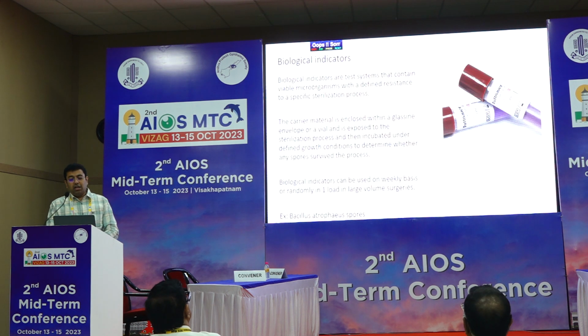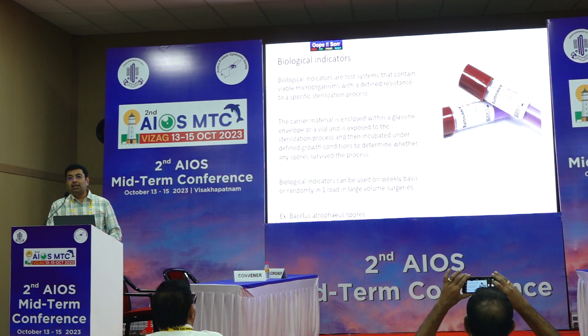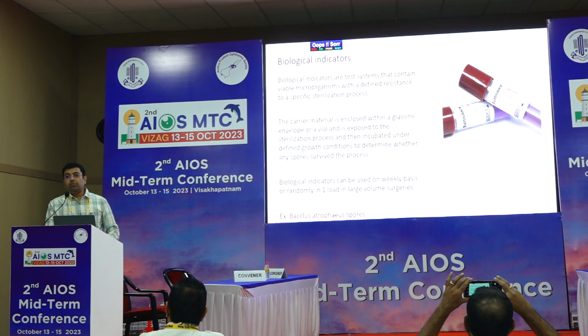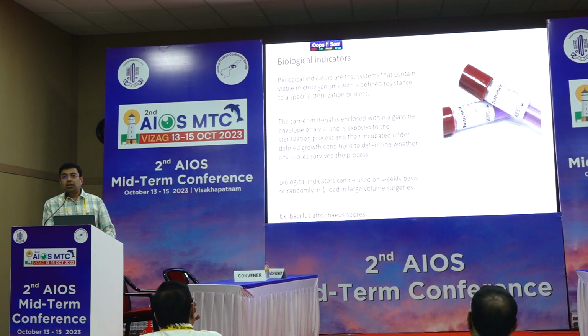Biological indicators usually contain viable microorganisms like Bacillus atrophaeus spores, and when these spores are exposed to higher temperatures, they get killed. These biological indicators, after sterilization, can be sent for culture, and once your culture comes negative, then you are pretty sure that your sterilization is working fine.